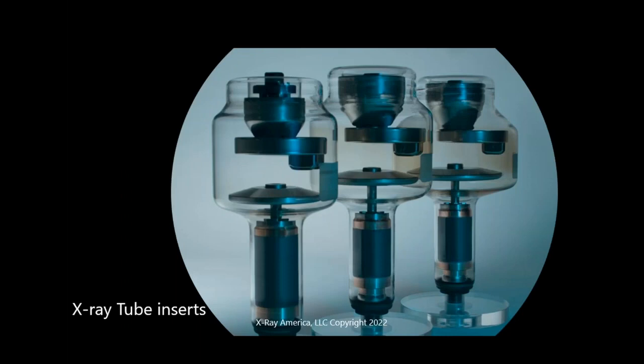Most X-rays. So we're going to talk about rotating anode diagnostic X-ray tubes. All these concepts will hold true for stationary anode X-ray tubes, smaller tubes, lower power, used in dental systems, and a lot of the concepts will hold for CT in general, although there's a lot of variations in the CT world.